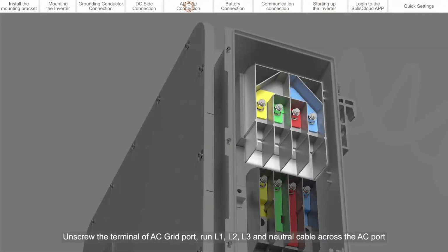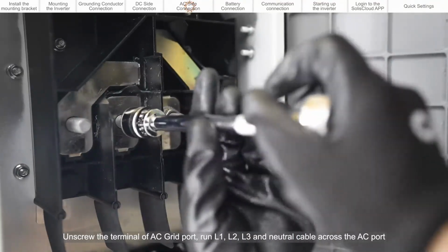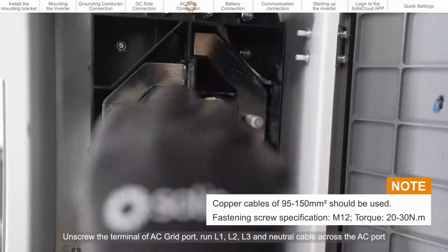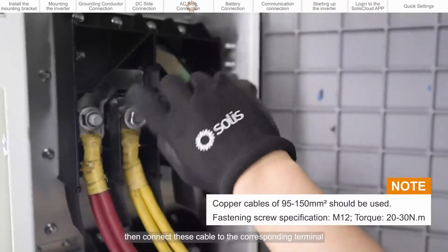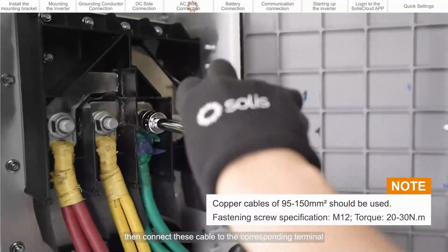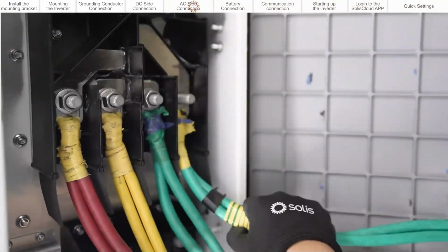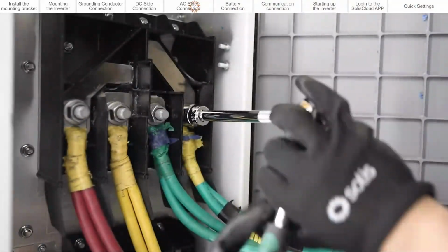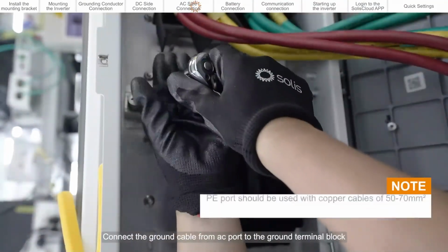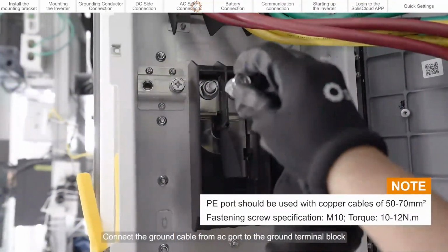Unscrew the terminal of AC grid port. Run L1, L2, L3, and neutral cable across the AC port, then connect these cables to the corresponding terminal. Connect the ground cable from AC port to the ground terminal block.